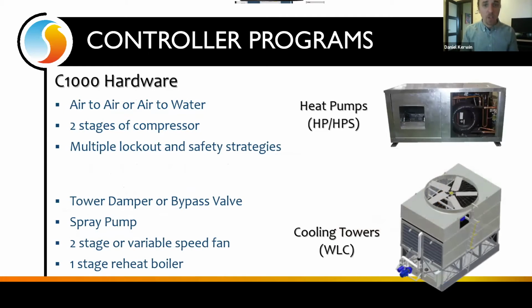Here's our heat pump controller, which can take care of either air sourced or water sourced heat pumps. It can control up to 2 compressors with additional supplemental heat if ever we needed it. If we have a building with a water loop going in it, and that water loop is feeding water sourced heat pumps, we can control the water loop temperature as well. If ever there's a little cooling tower system with a boiler, we are able to manage that as well.